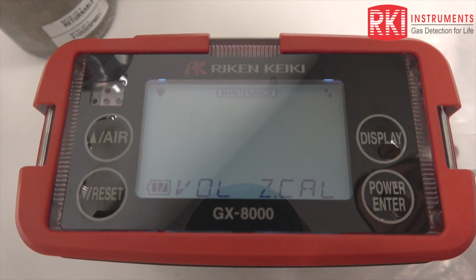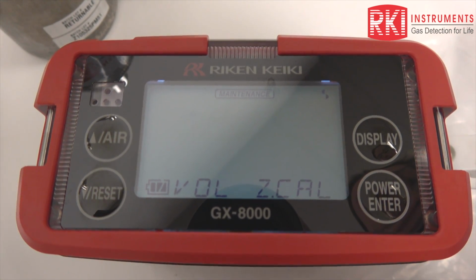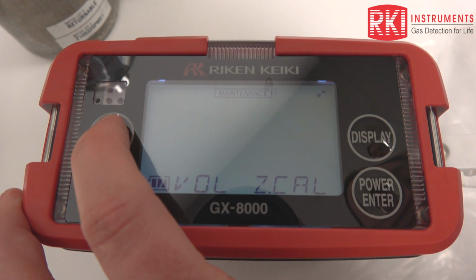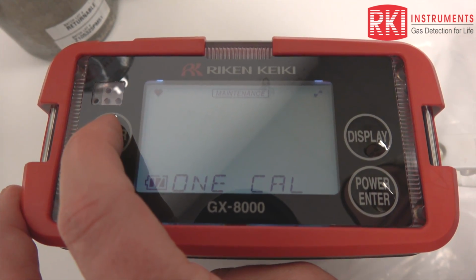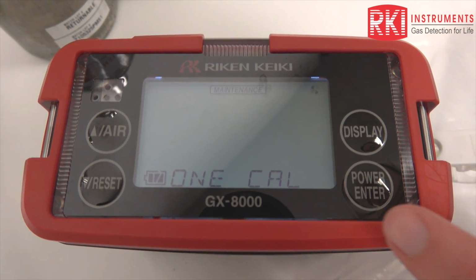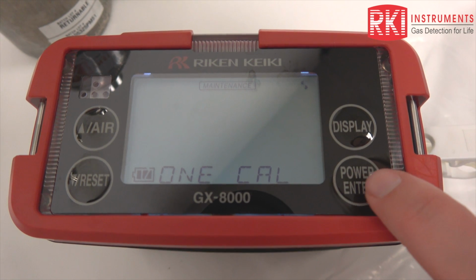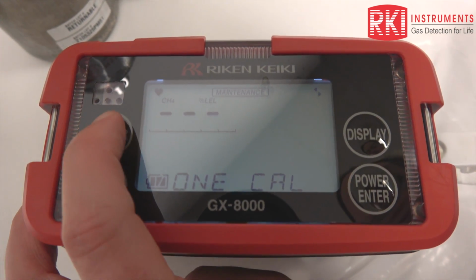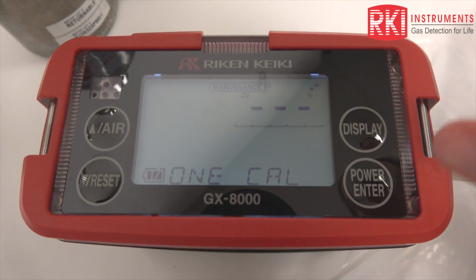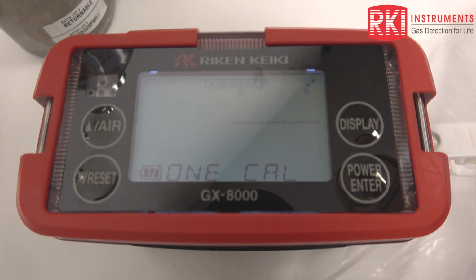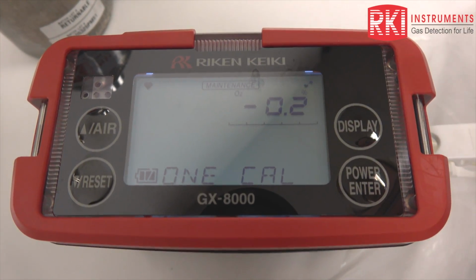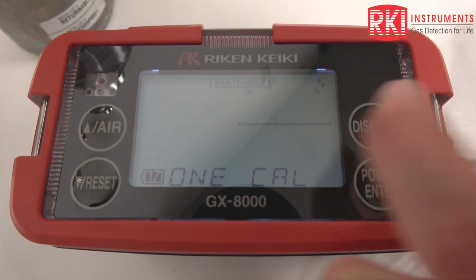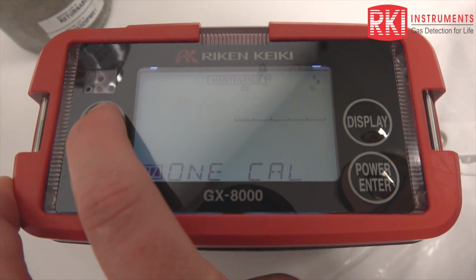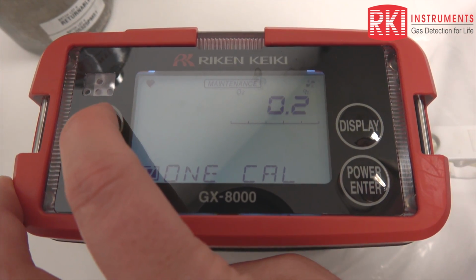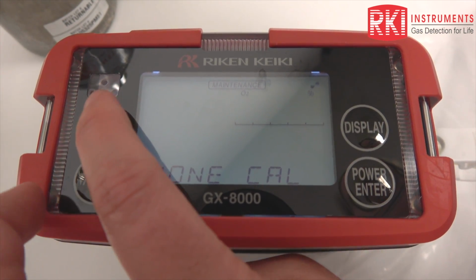And my 0 cal for the volume sensor is done. I'm going to now calibrate my oxygen sensor since I already have nitrogen in my gas bag. So I'm going to go to 1 cal, press power enter, scroll to oxygen, which is here, press power enter. This is the reading from my gas bag. It actually says minus 0.2.